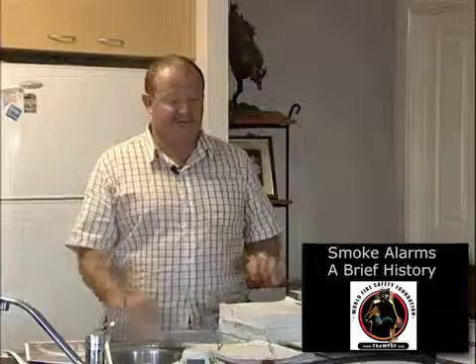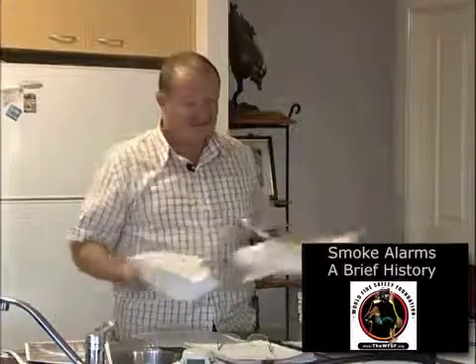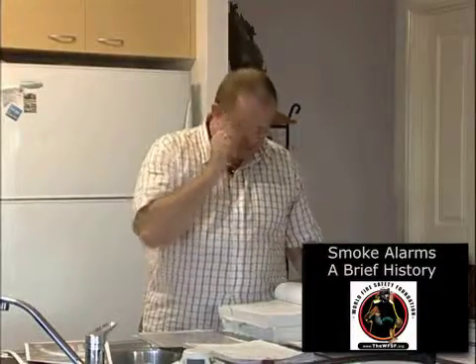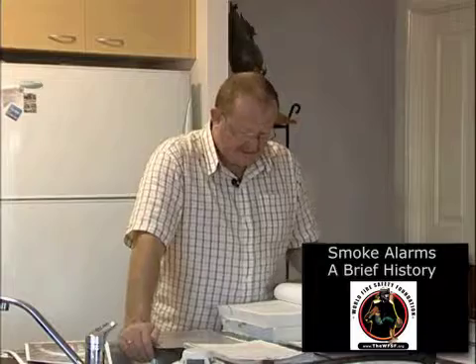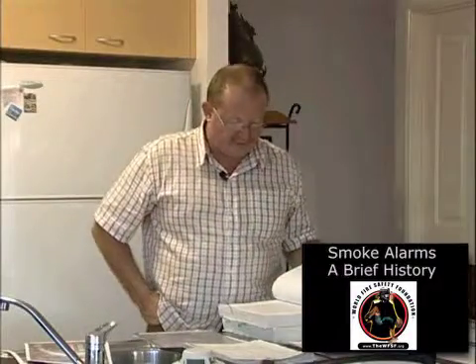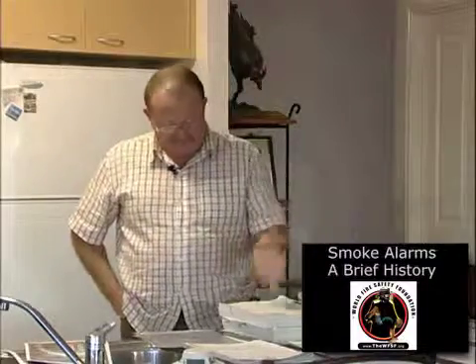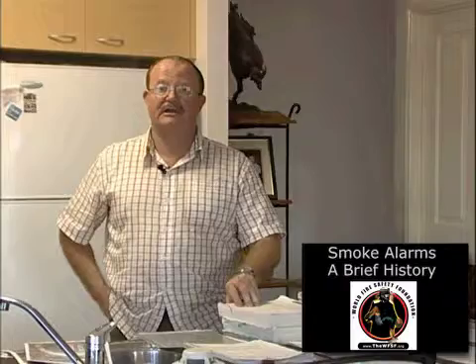At this stage, the government thought they'd better do some testing, as there had been no formal government testing of smoke detectors. So in 1974, the US government funded the DUNES test, done in the Indiana Dunes Wildlife Preserve. It took two years. After two years, the conclusion of the test stated: 'A residential smoke detector of either the ionization or photoelectric type, set at the sensitivity levels encountered during this study, would provide adequate life-saving potential under most residential fire conditions when properly installed.' Most people who looked at these tests went straight to the conclusions and accepted them, because surely no one would falsify test results.